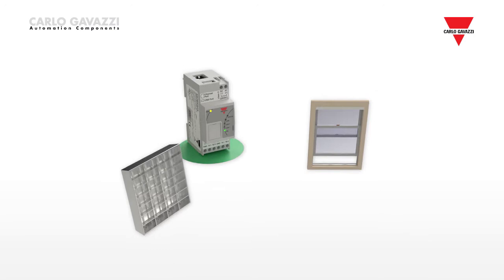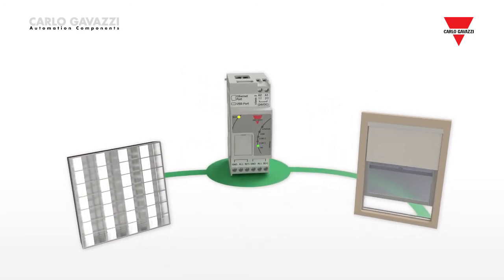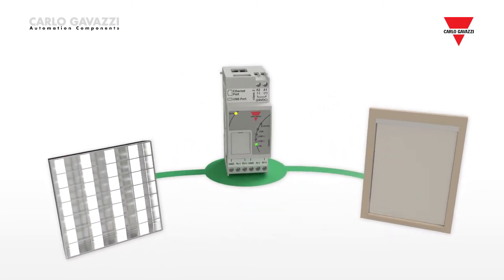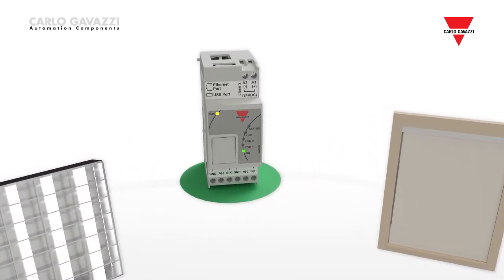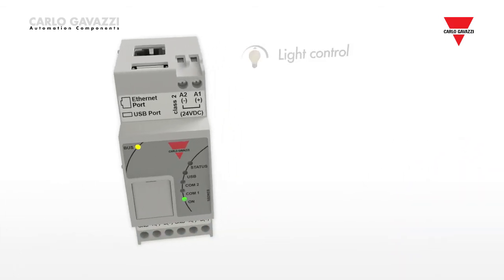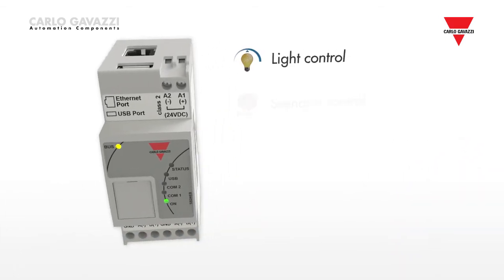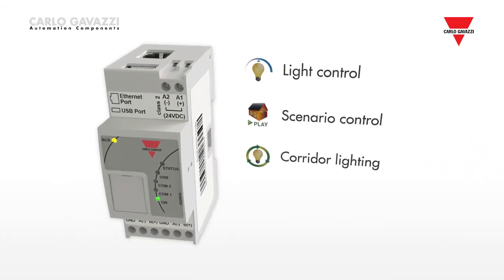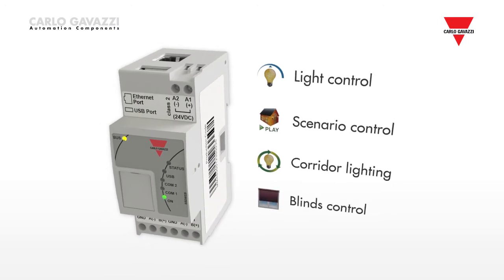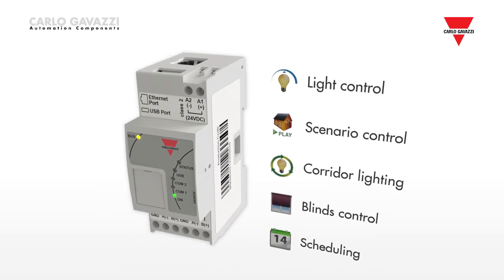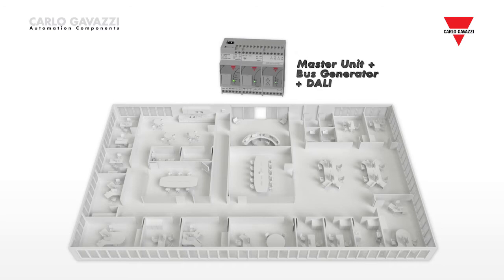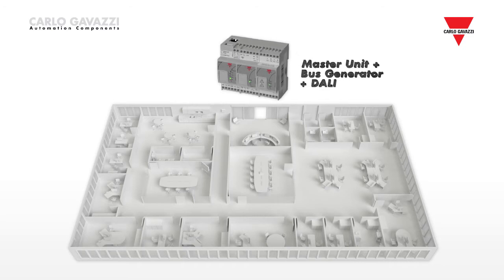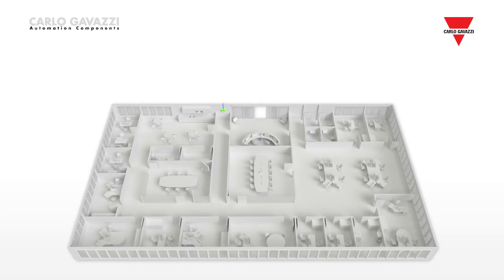For lighting and blinds control, the SB-Web BACnet controller runs the strategy. This includes functions such as constant light control, scenario control, corridor lighting, blinds control and scheduling. The interface to the dimmable lighting loads is implemented through the DALI bus, the standard for lighting actuators.